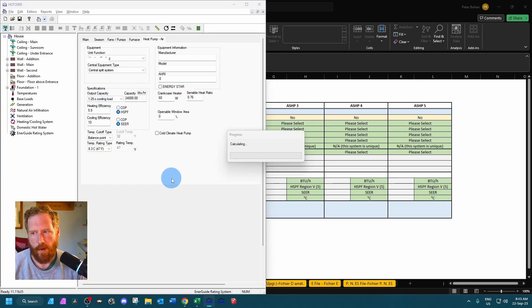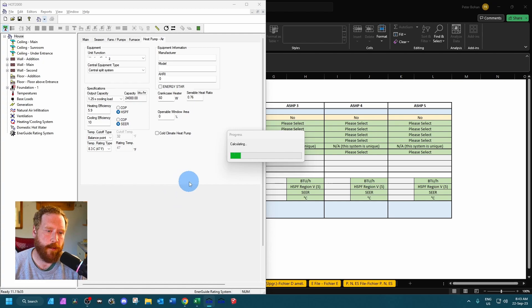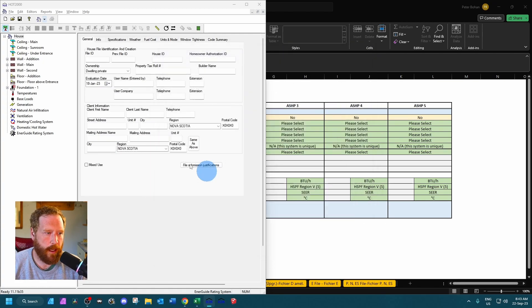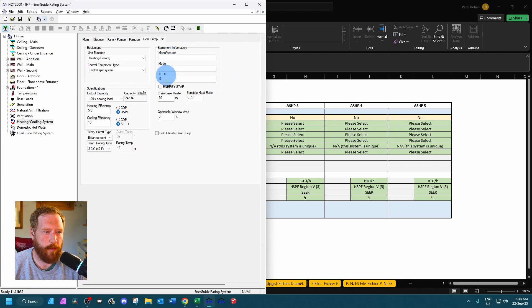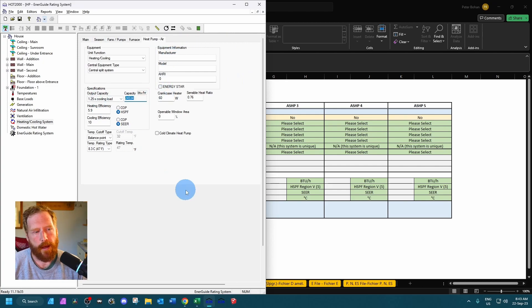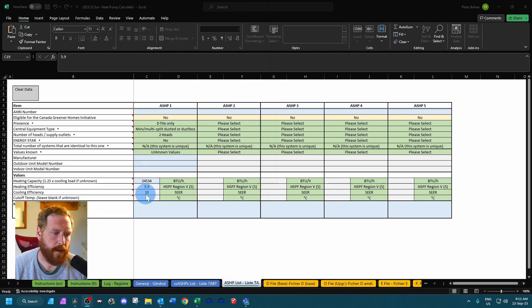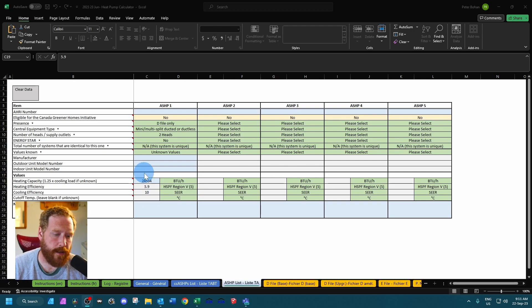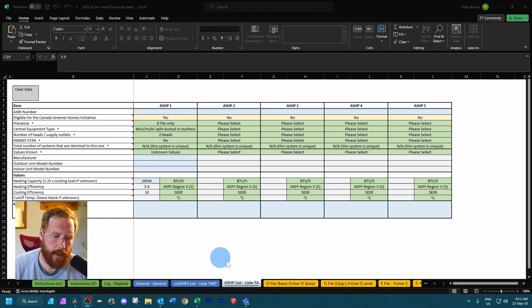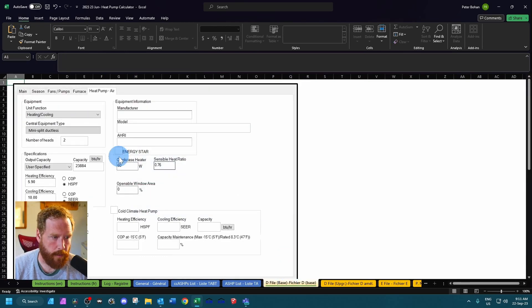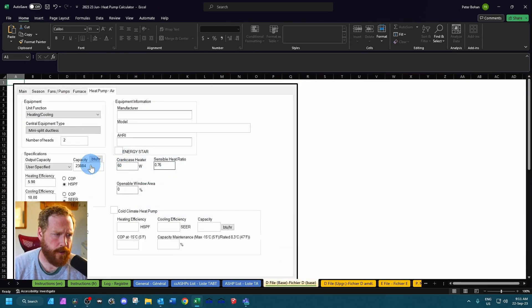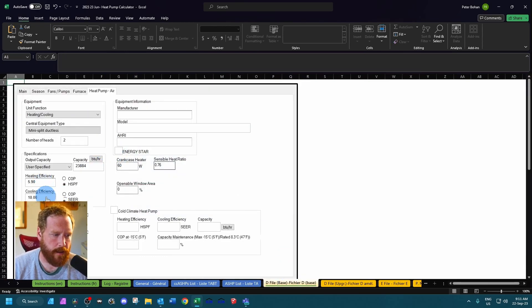And then what we would do on this tab is go and select 1.25. We're going to hit Alt+C, wait for the pop-up to come up. Then we're going to close it down, so we just click OK. Go back to our heating and cooling system, to our heat pump. And it's going to give us a capacity of 23,884. So then we enter that into the calculator on the ASHP tab. And then you can see here it's going to tell us this is how we model it. We're going to put in actually a slightly reduced capacity, same HSPF, same SEER. Leave it at balance point.